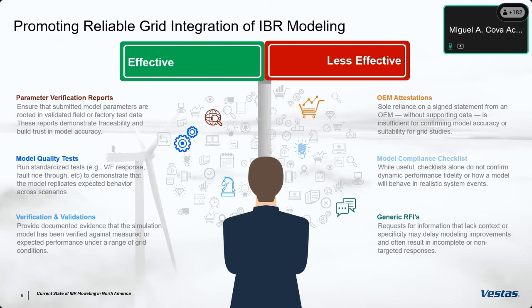Model quality test—I've used the name from ERCOT, but you can call it whatever. I know Nova Scotia uses a different name, Hydro-Quebec uses a different name, but basically it's a certain procedure that aims to prove the robustness of the models. This is really important because it's not only that the model has specific performance matching the actual product, but also that the model is robust enough under certain conditions that sometimes aren't even evaluated during the grid interconnection process. And then there's verification and validation.